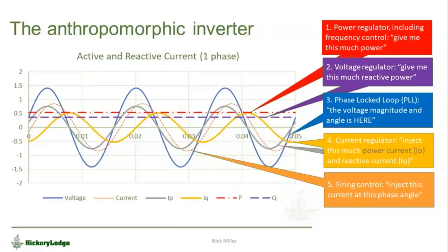The next critical piece here is that the inverter needs to know when to inject the current, and the way it does that is it uses a phase lock loop. That's the blue line. The phase lock loop measures the voltage—not just the magnitude, but critically, where that sinusoid is in time—so that it can instruct the active current IP and reactive current IQ, the gray and yellow lines, to be injected at the right magnitude. Those are added together, and finally the power electronics trigger to inject current at this angle. That's how we get that orange line, through those five steps.